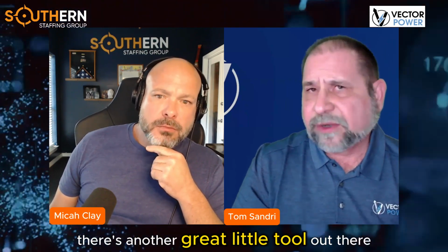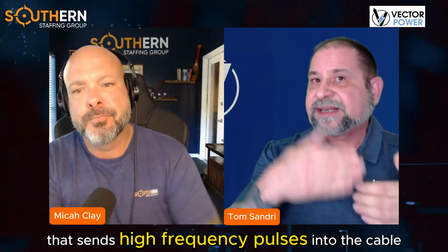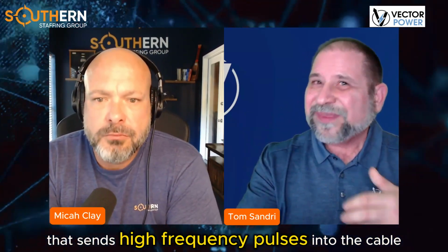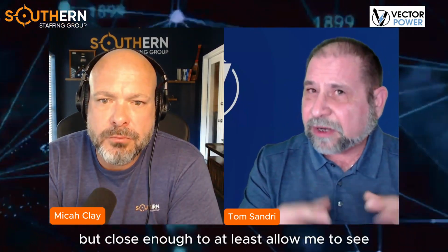Or if I don't want to take the full PD kit and pulse calibrator out, there's another great little tool called a time domain reflectometer. It sends high frequency pulses into the cable, slightly lower frequency band, but close enough to let me see how receptive your circuit is to high frequency transmissions.